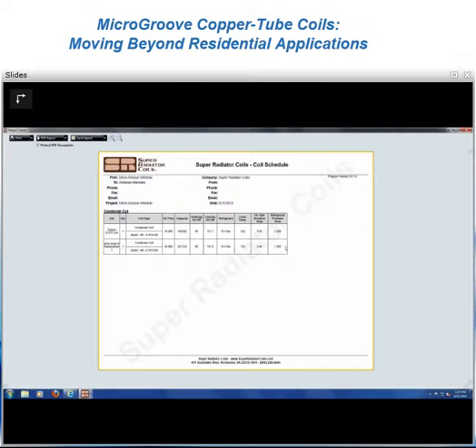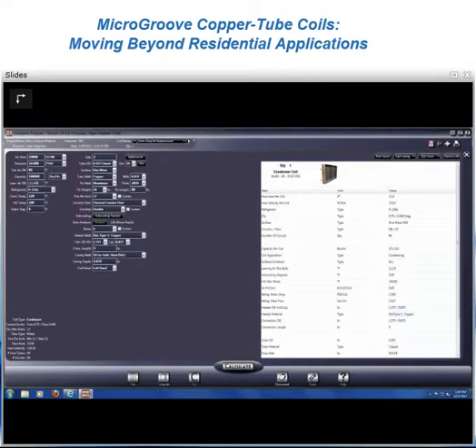What you don't see on the screen is the real power of the 5mm coil, and that's this. The refrigerant volume of the 5mm coil is 54% less than your existing 3/8 coil. That's significant. The coil weight overall is down by 32%. It's now 102 compared to 150 pounds. And the copper weight is down 53%. Same performance, less air friction, and I'm saving 53% on my copper weight. So if you just want to not change your footprint, drop-in replacement, that's one thing that 5mm can do. What else might we do?